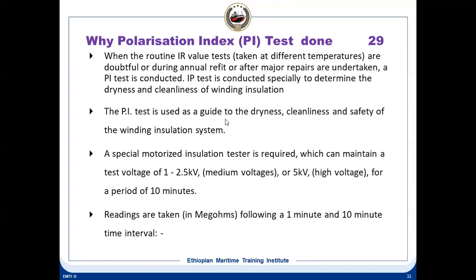The purpose of the polarization index test is to determine the winding dryness, cleanness, and any moisture content on the winding. That is the purpose for carrying out the polarization index test. So what is the purpose of the PI test? It is to gauge the dryness, cleanness, and safety of the winding insulation systems.